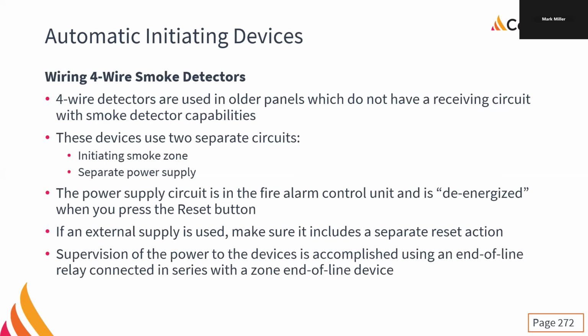So our four-wire smoke detector, which I briefly mentioned, we use them in older panels which do not have initiating circuits that are capable of using smoke detectors. We also use them if we need to run a lot of relay bases, or if we need to just put in a very large number of smoke detectors. We might have to use four-wire smoke detectors. We might be able to avoid putting four-wire smoke detectors in the entire zone. Maybe the second half gets the four-wire smoke detectors. The first half, we're fine with two-wire smoke detectors, just pulling power off of the initiating circuit. Right? It'll depend on the nature of the system.